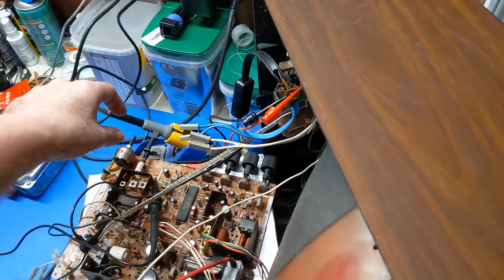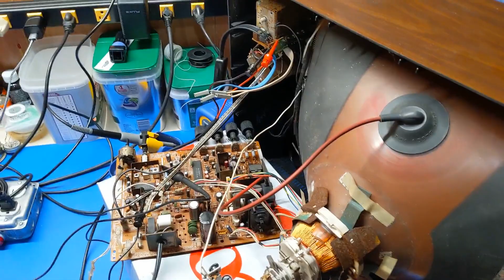Now, the reason why I want to bring this up is there's a phenomenon called dielectric absorption. So what happens is now everything's been removed, right? It was safe to remove it. I didn't get shocked or anything like that. But now that it's been sitting for a second, if I turn this switch back on and touch that cap again, you see that little voltage creep up right there? And if I let it sit some more, I'll get more voltage creep up. I can still feel the static cling. So this has absorbed energy.